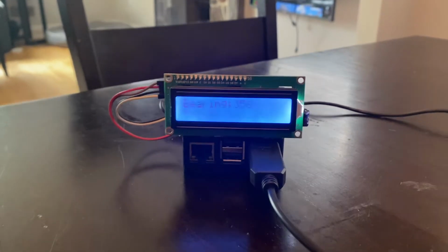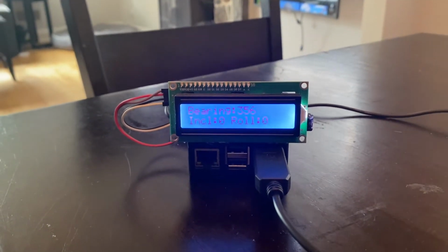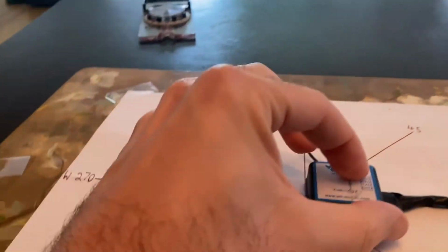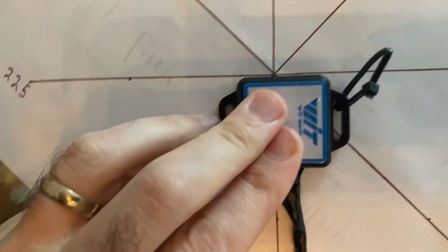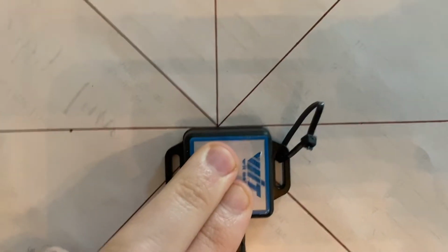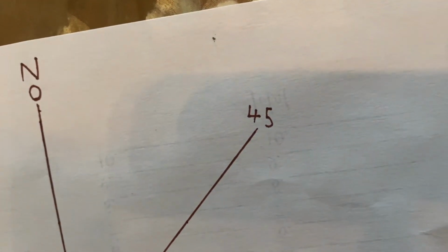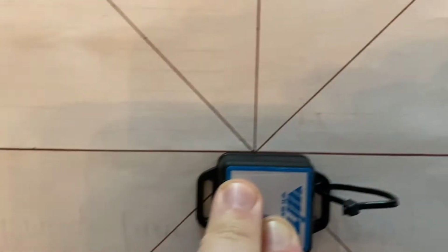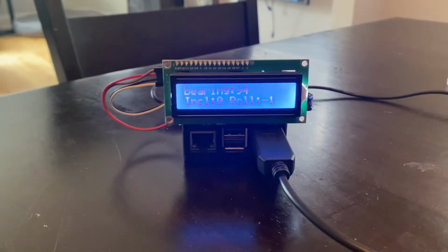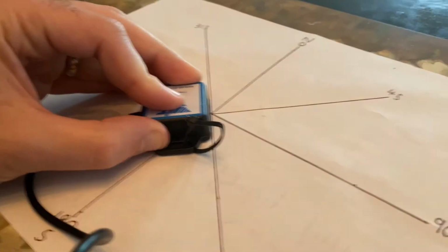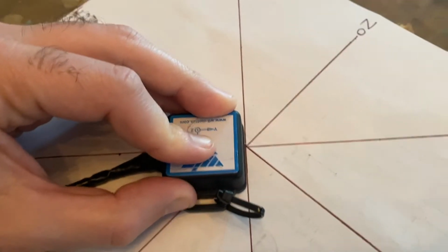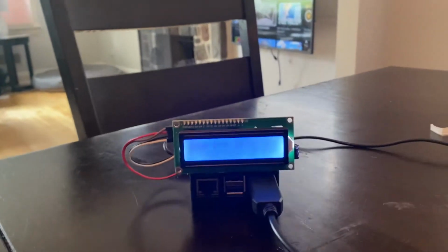Look here, showing 356. So it's under by 4 degrees. As we rotate it around, here you can see it should be 45, showing 46. So it's now 1 over. Here we have it lined up exactly on the 90, showing 94. So it's now 4 degrees over. Have it lined up exactly on the 135, showing 141, so 6 degrees over.